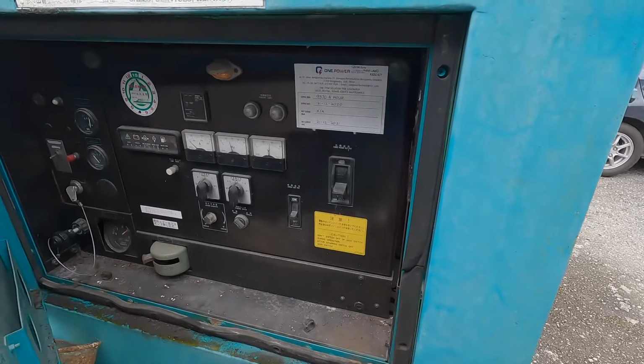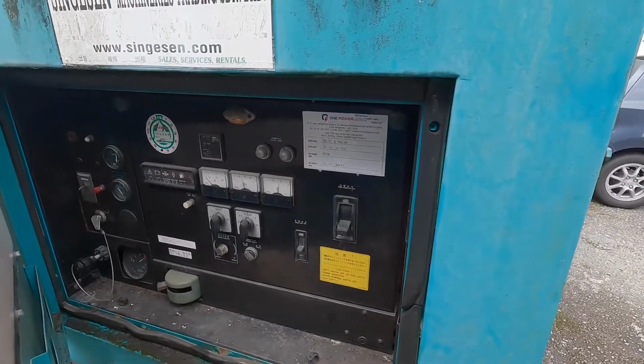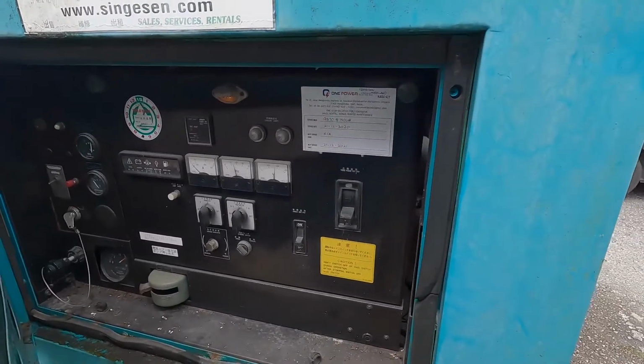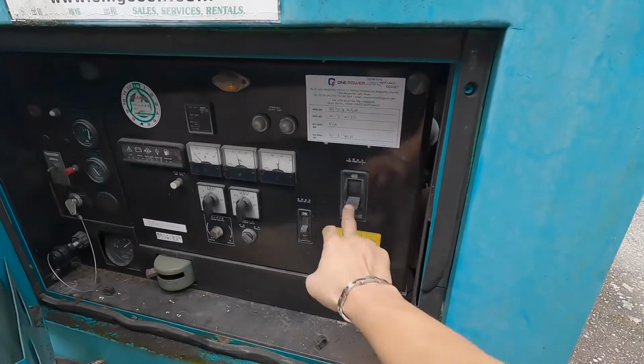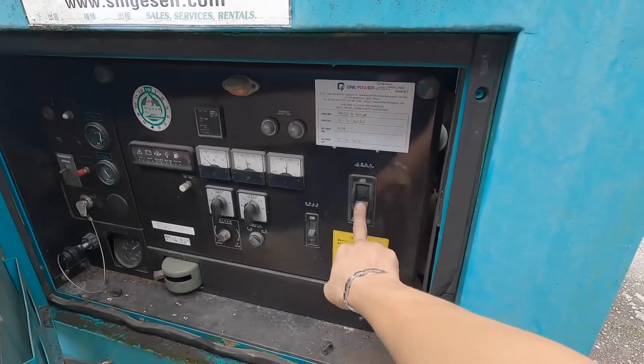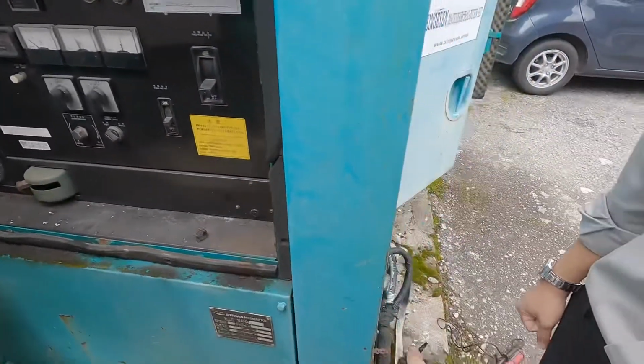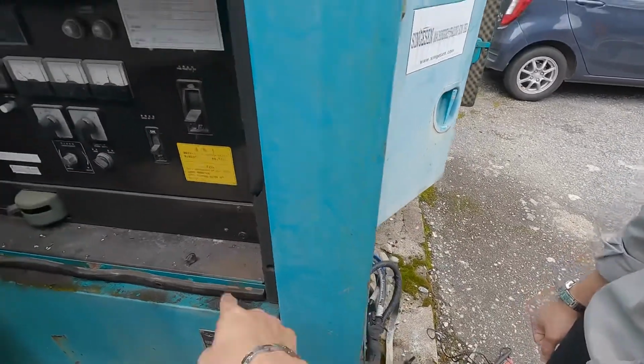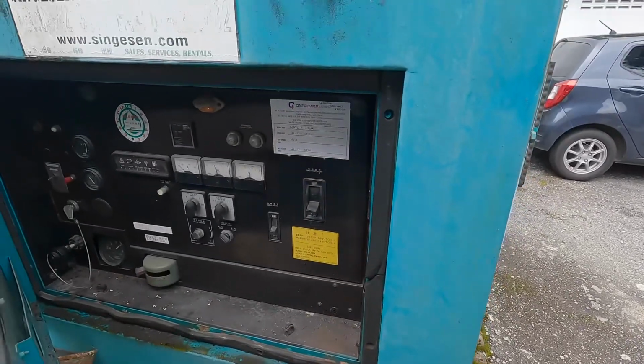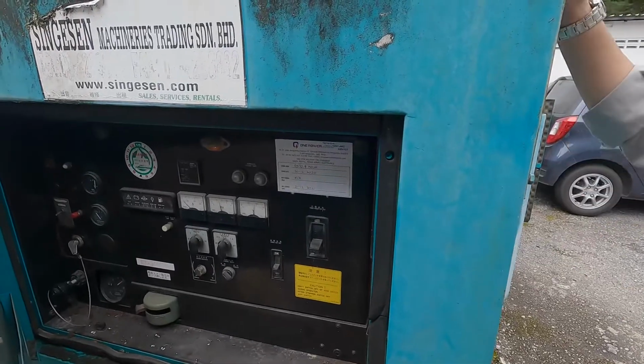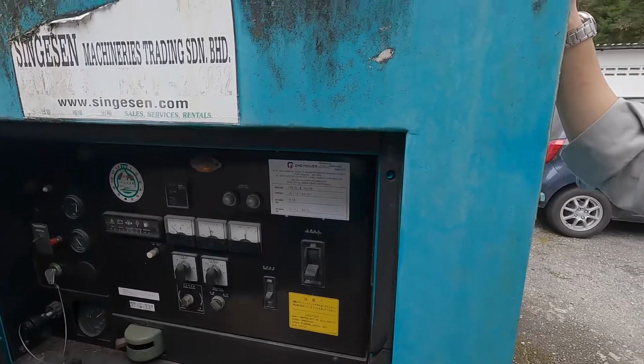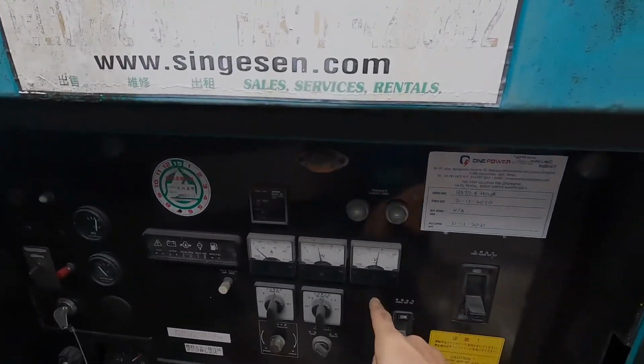Okay, no power supply reaches the genset ATS panel because this outgoing is off, but we don't know why it's being off. Maybe because this cable got some problem, so they off it. Okay, so from here we're going to test the voltage, see what the voltage is.